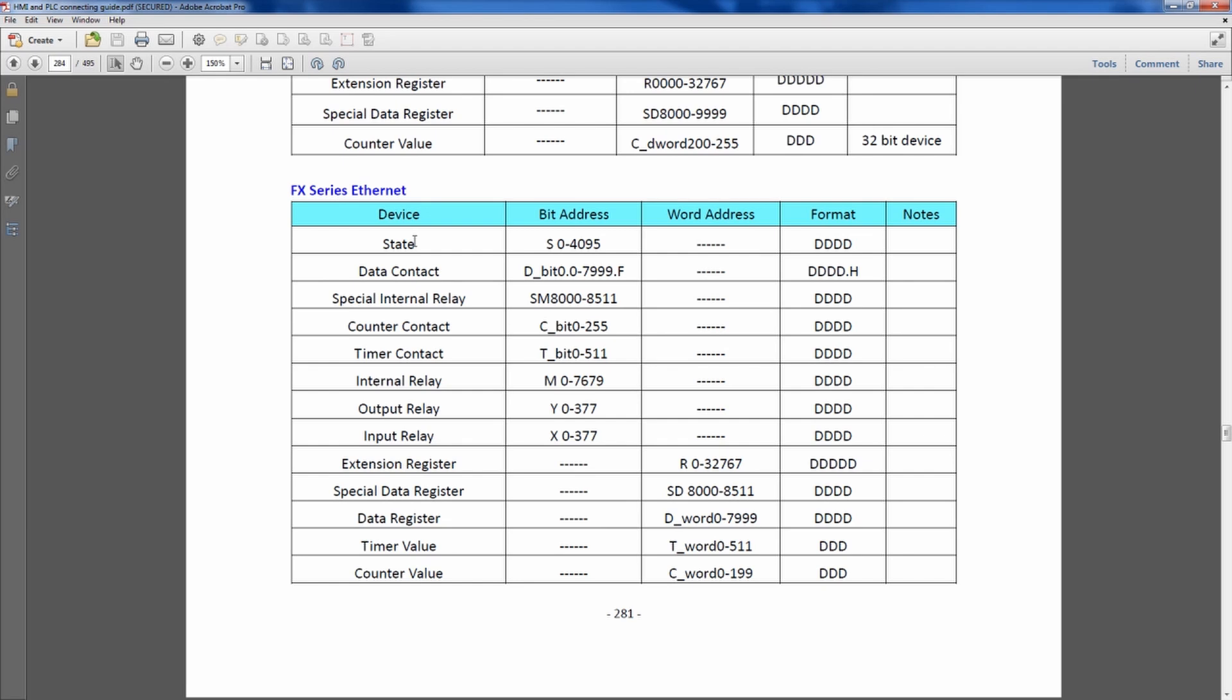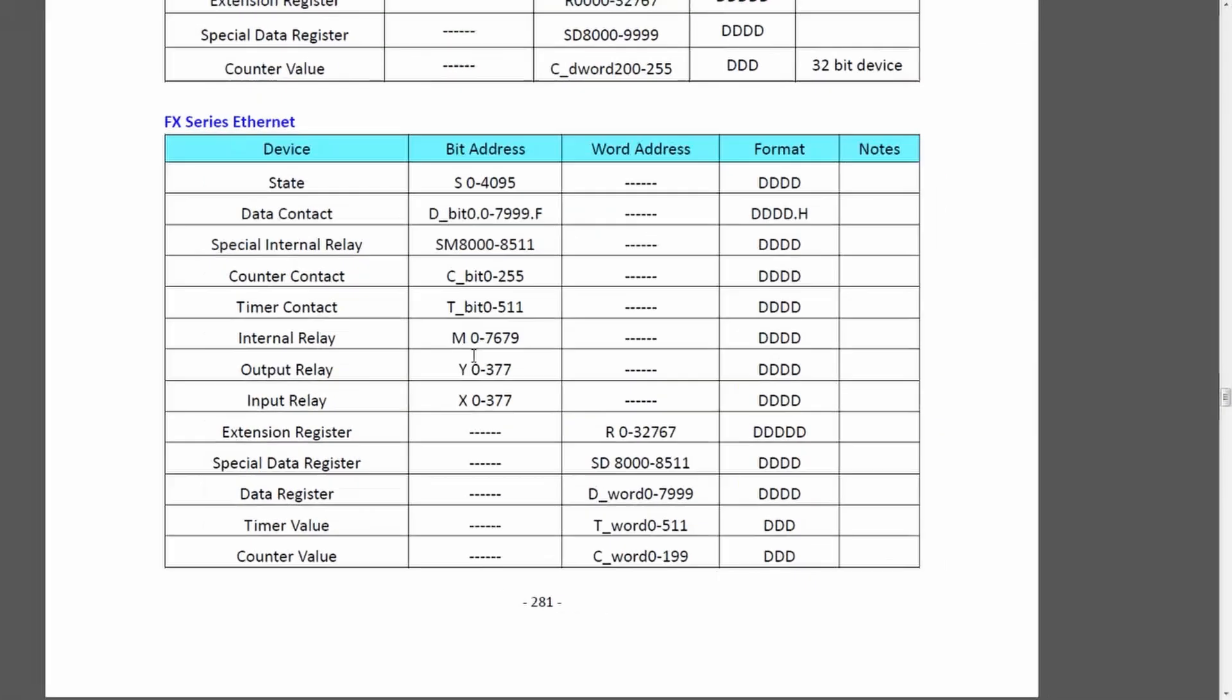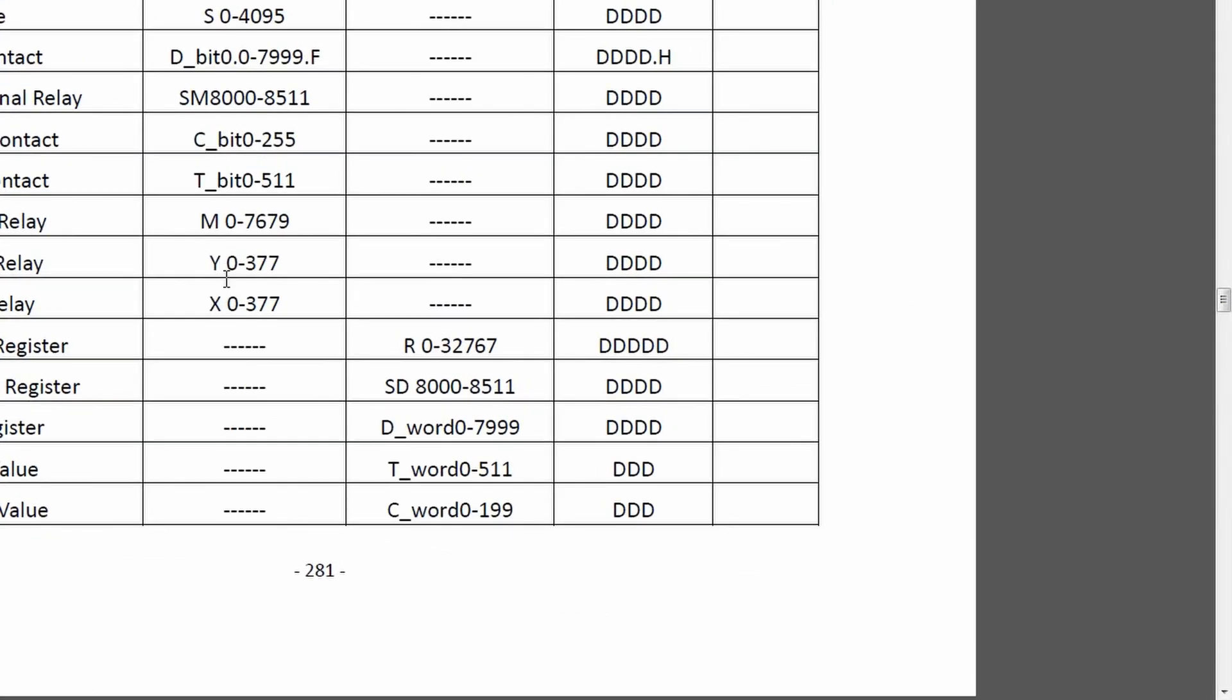What you notice here is that you have state relays or state coils. Those are 4096 long and they show you the format of it. You have the zero state. If you're using like an STL, you'll have these different contacts. It won't map pointers. You'll notice that there's no pointers mapped here, but there are counters and counter contacts, internal relays, input relays, output relays. And Mitsubishi does say input relays are mapped with modifier X or mapped with a modifier of Y for an output relay.